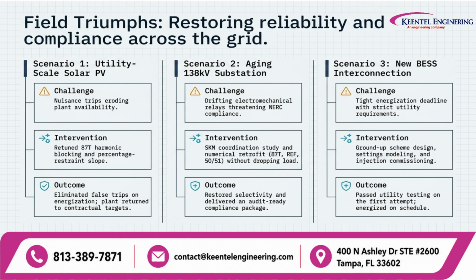The third scenario involves a new BESS interconnection. The challenge was a tight energization deadline combined with strict utility requirements. The response was a ground-up protection scheme design, settings modeling, and injection commissioning. The result was successful utility testing on the first attempt and energization on schedule.